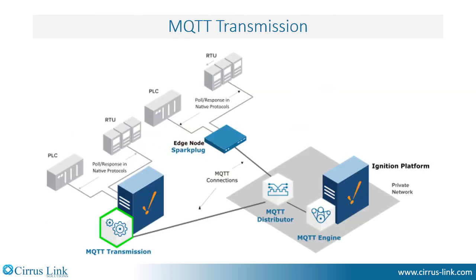Just to recap, the MQTT transmission module, as highlighted in green in this picture, is installed on the Inductive Automation Ignition platform. It takes any tags within the Ignition tag tree, including complex data types such as UDTs, and transmits them to an MQTT server in the MQTT Sparkplug payload format.